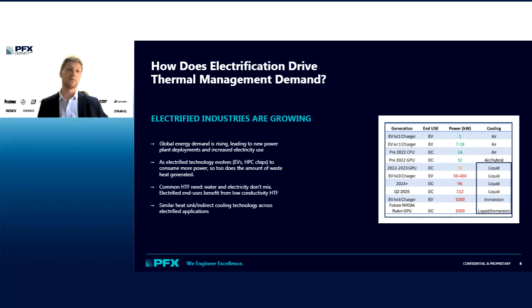The story is the same on the electric vehicle side. Level 1 and level 2 chargers can use passive cooling because there's not an extreme amount of current flowing through, but with these chargers you're waiting 6 to 12 or more hours for your vehicle to be fully charged. As we move to level 3 and level 4 chargers, we demand liquid cooling again. The majority of level 3 chargers, which can charge your vehicle in under an hour, are liquid cooled to dissipate that heat and avoid damaging components from excessive heat.